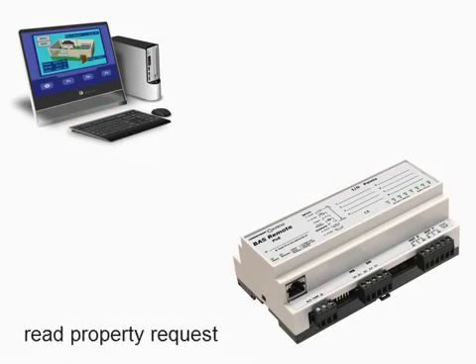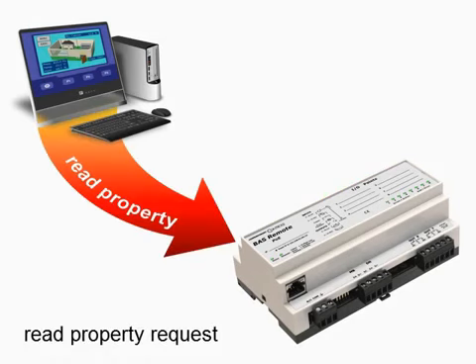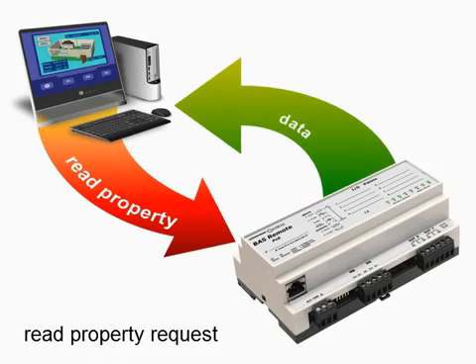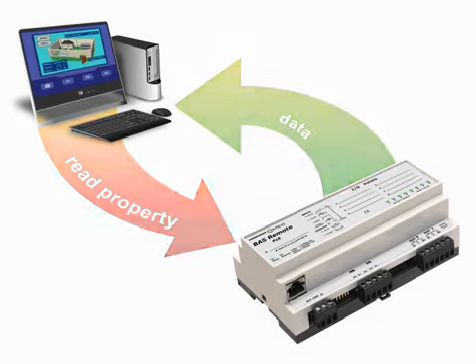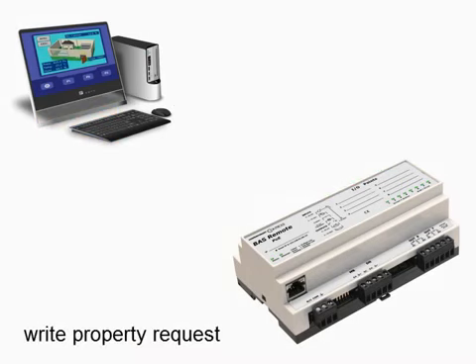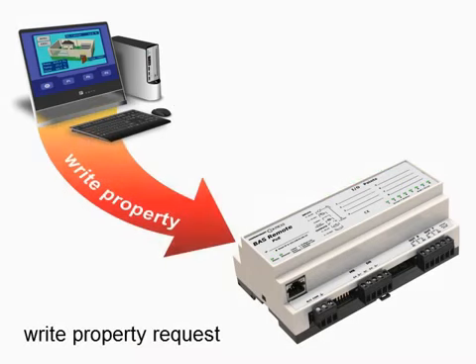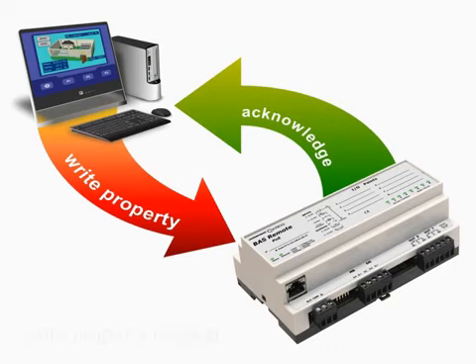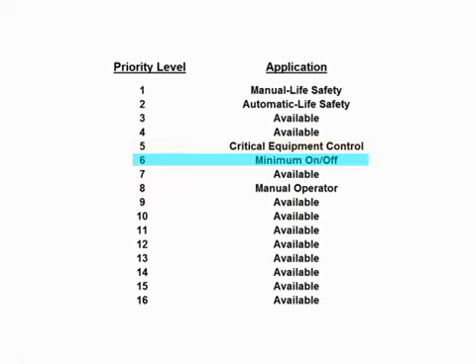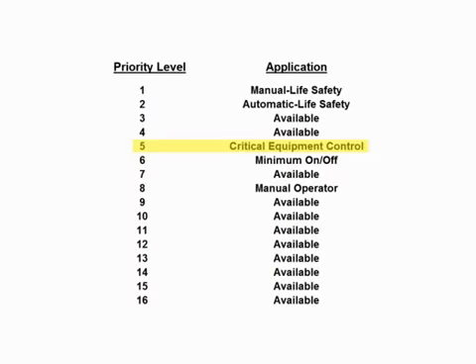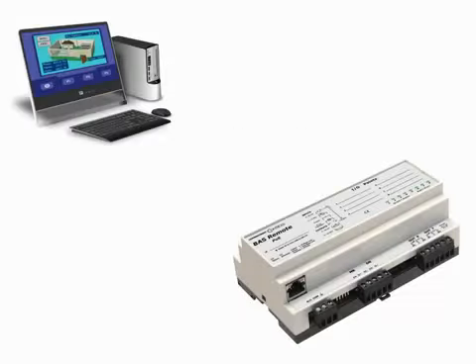In a read property request, the server will provide the value of the property indicated. In a write property request, a value is sent that changes the indicated property. Up to 16 levels of priority exist when writing values, thereby allowing for one client to take precedence over another. If two clients are writing to the same server using the same priority level, the last value sent will be stored.